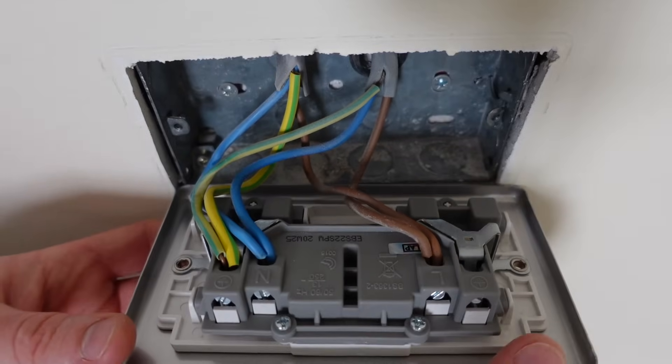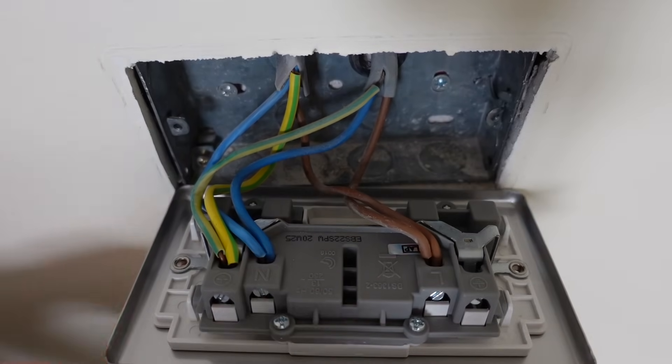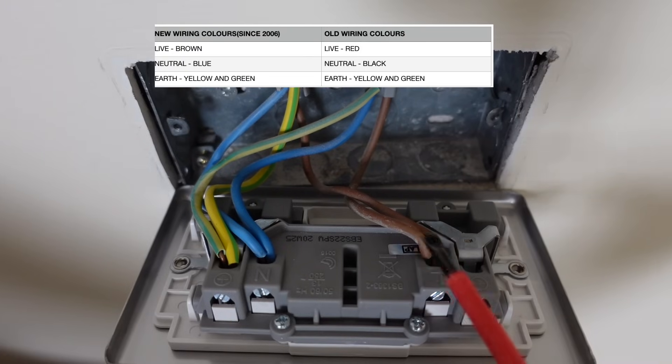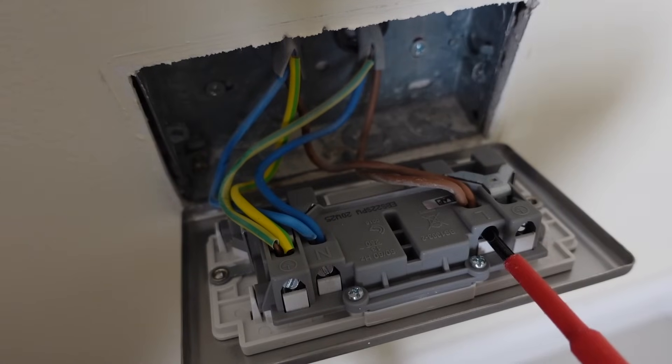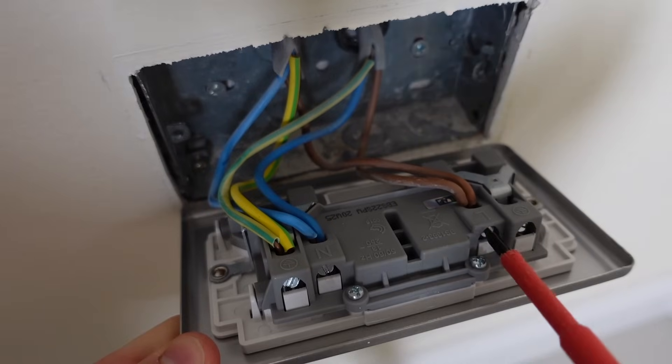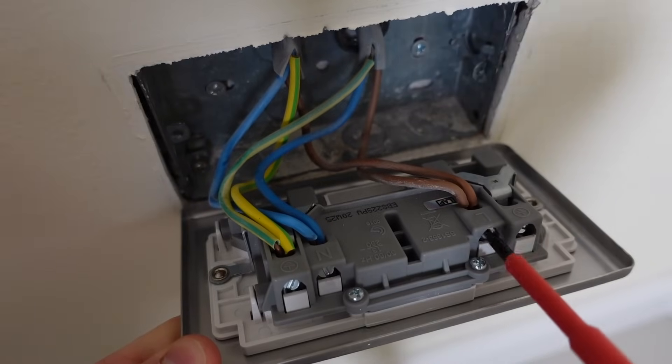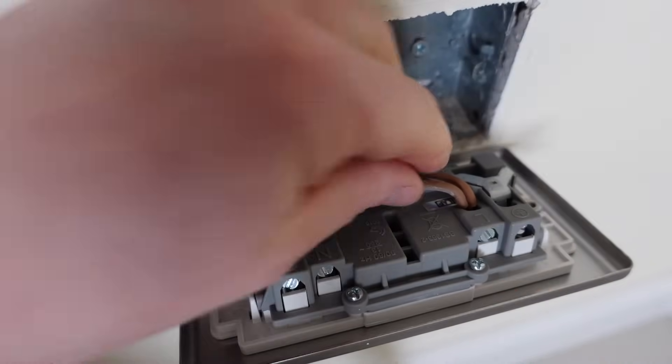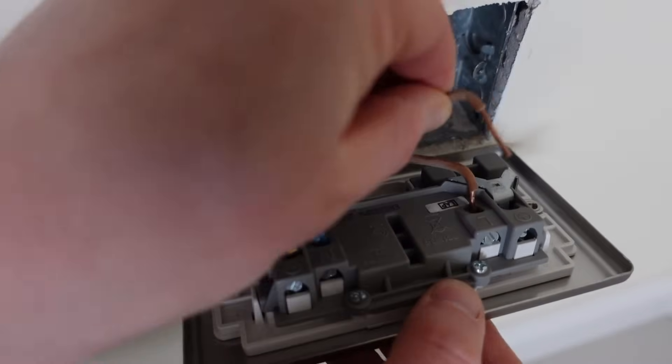Just make sure you've got good access to the back of the socket and begin to undo some of the terminal screws. In this case we have the new color wiring so we've got brown for live, blue for neutral and green and yellow for earth or CPC. So first of all we'll undo the terminal screw on the live wire, that's the brown one, just undo that little terminal screw and then you'll be able to pull the wires out the way.